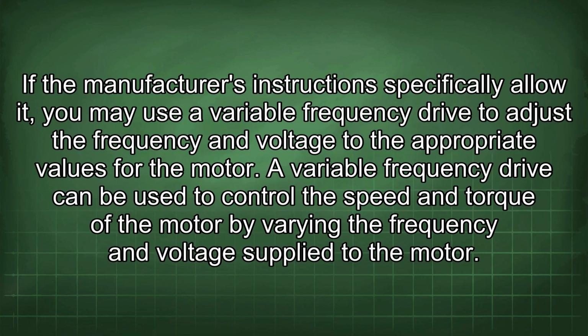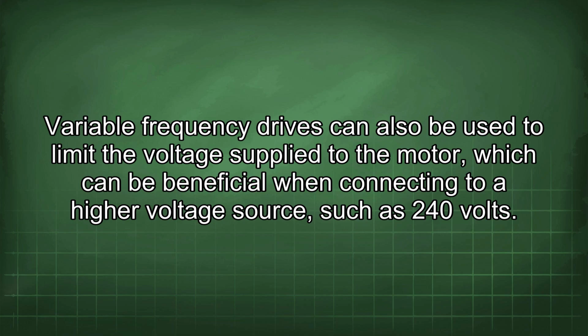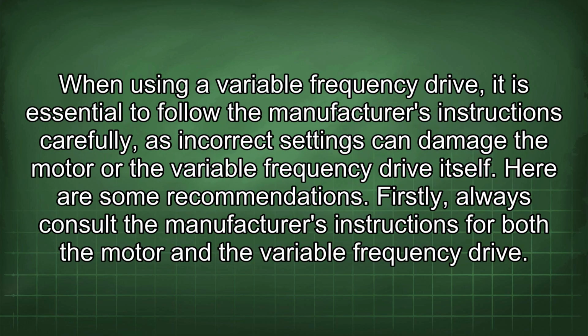If the manufacturer's instructions specifically allow it, you may use a variable frequency drive to adjust the frequency and voltage to the appropriate values for the motor. A variable frequency drive can be used to control the speed and torque of the motor by varying the frequency and voltage supplied to the motor. Variable frequency drives can also be used to limit the voltage supplied to the motor, which can be beneficial when connecting to a higher voltage source, such as 240 volts. When using a variable frequency drive, it is essential to follow the manufacturer's instructions carefully, as incorrect settings can damage the motor or the variable frequency drive itself.